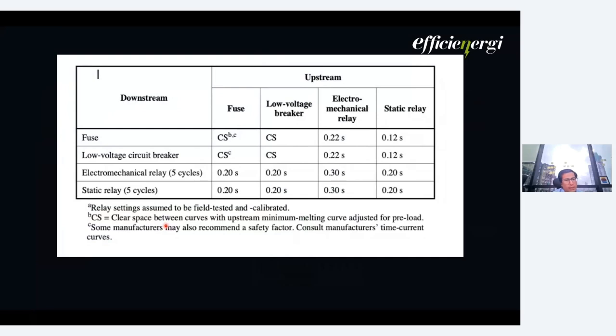So this is taken from the 242 standard. When we are working with a low voltage circuit breaker, it is just saying that a clear space is required. Because it is a banded curve, the tolerances and everything are covered. So minimum and maximum are explained by the curve itself. Our duty is only to have a small clear space between the two breakers.